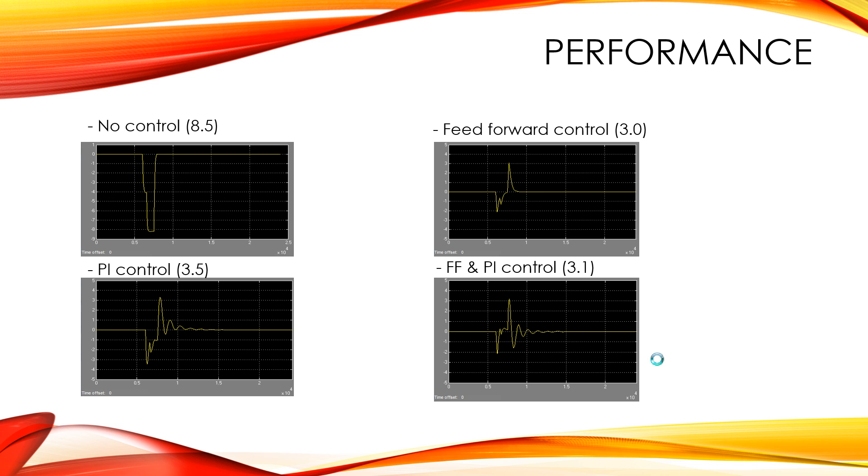Luckily, feedforward control is actually very good at responding. The only reason why we integrated it with a PI control is because it kept it better. You actually have a quicker response right here. You can see that it responds a little bit faster, where the feedforward alone stays a little bit farther away from set point.